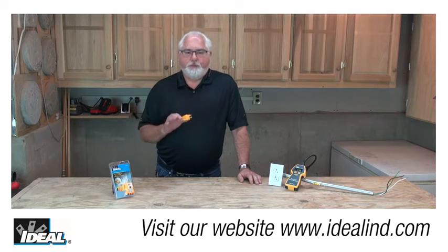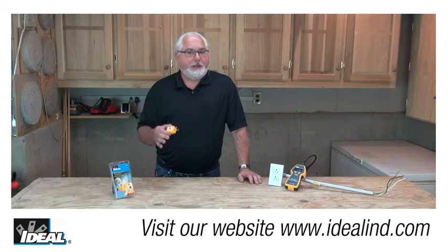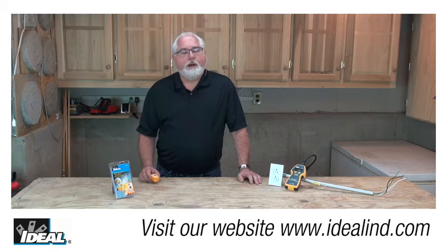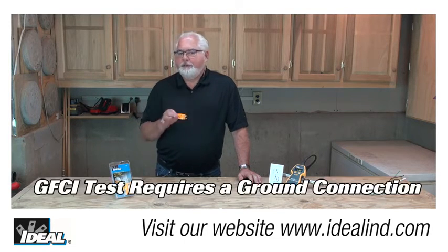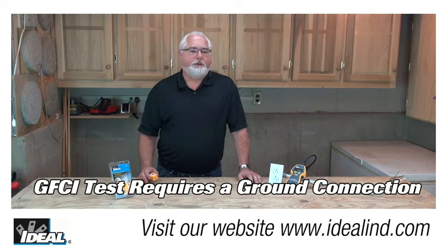Now, if both bulbs do not go out and the GFCI does not trip, it can suggest a wiring problem with a good GFCI, or it could be good wiring with a faulty GFCI, so you'll just have to check it out. And this test also requires that the outlet be wired with a functioning ground conductor.